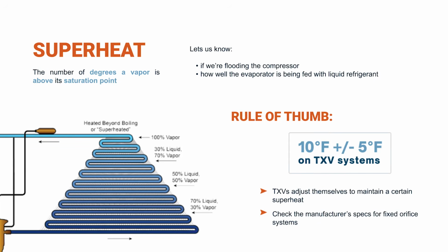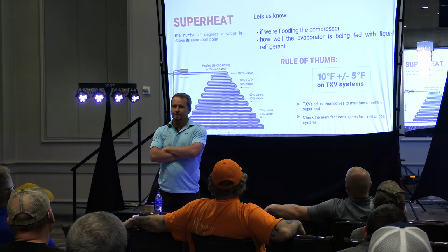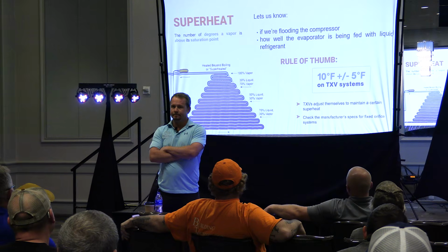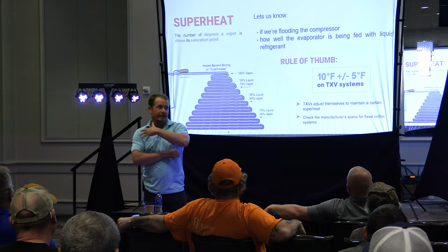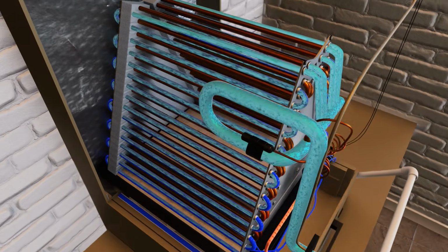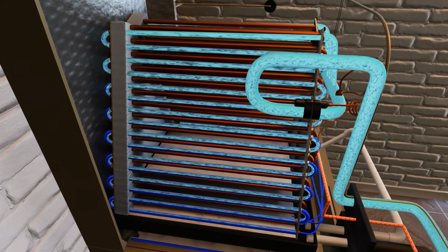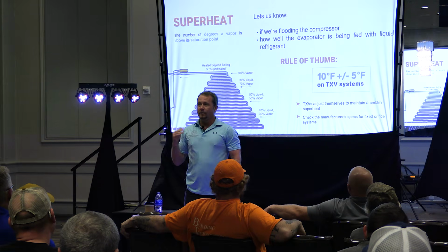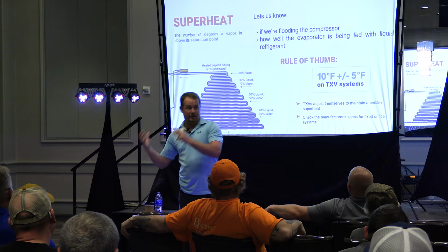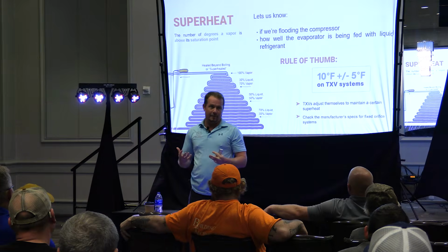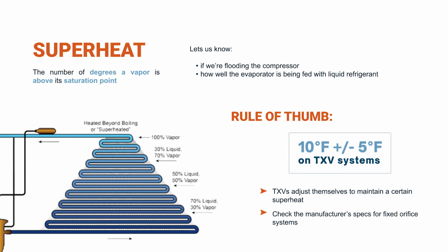Superheat. We're going to talk quickly about it. What is superheat really telling us? What is it indicating to us about the system? The amount of liquid that's in the evaporator. Yeah, that's a really good way of thinking about it. That's the way that I talk about it in the videos. Imagine refrigerant stacked in that evaporator coil. How full is it? As a heuristic, our suction saturation, our evaporator temperature, tells us the temperature of the evaporator, and our superheat tells us how full it is. You know those two things, now you know what you need to know. You can't just know one or the other because that doesn't tell you enough.